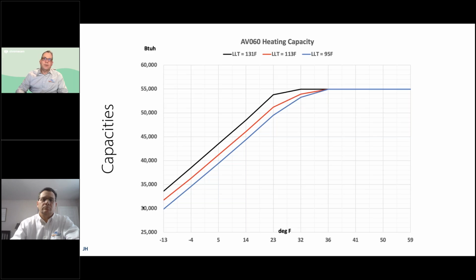And likewise, we might be a COP of 1 at 0 degrees outside. So not only is the COP twice that of an air-to-air heat pump, but the capacity is significantly higher as well. With the backup heater or the backup boiler, then we can pretty easily handle that load even at the very cold temperatures. It'll be really important to use the software. We have the GeoAnalyst software available that we'll be talking about shortly, so that we can size it appropriately and look at the best size for that application.